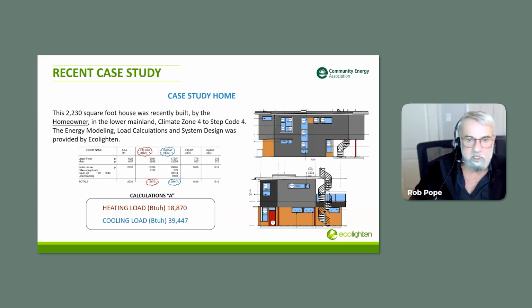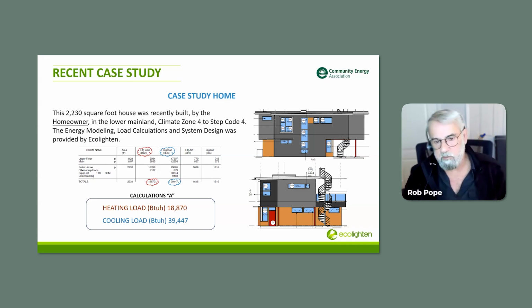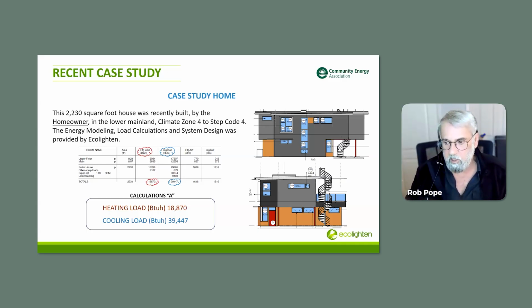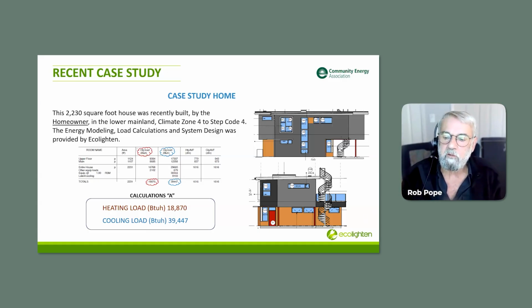It's in the lower mainland in a small community, climate zone 4, built to step code 4. The energy modeling, the load calculations, the whole system design Ecolighten did was done in-house. This is what we came up with for the loads, among other things: heating load 18,870, and cooling load 39,000 - more than double. There's a lot of reasons for that, and we'll discover some as we go. Keep that in mind - that's what we came up with.